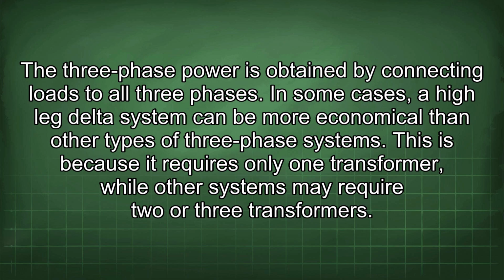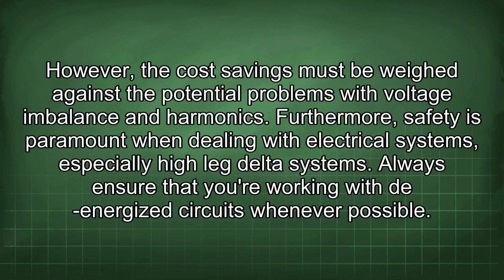In some cases, a high-leg delta system can be more economical than other types of three-phase systems. This is because it requires only one transformer, while other systems may require 2 or 3 transformers. However, the cost savings must be weighed against the potential problems with voltage imbalance and harmonics. Furthermore, safety is paramount when dealing with electrical systems, especially high-leg delta systems. Always ensure that you are working with de-energized circuits whenever possible.